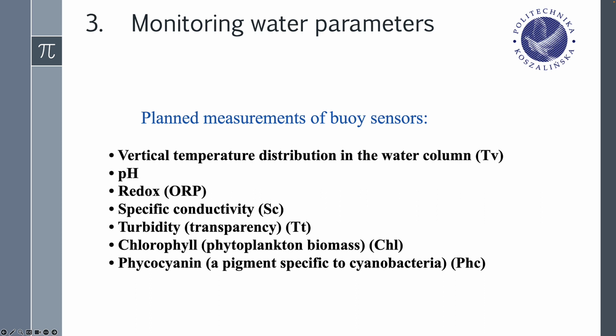Planned measurements of buoy sensors, vertical temperature distribution in the water column, TV. Temperature is one of the most important physical factors influencing the rate of reactions occurring in all ecosystems, including aquatic ones. Temperature also affects the value of other parameters, including electrical conductivity. The device automatically compensates the conductivity level to a value of 25 degrees Celsius.